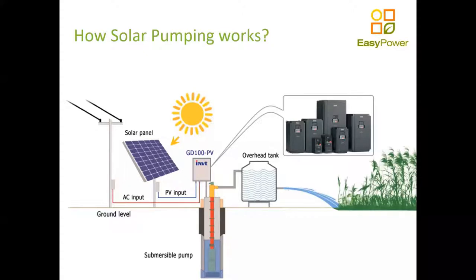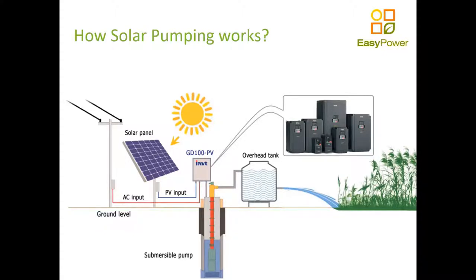The pump inverter drives the pump by changing the frequency, voltage, and output. When utilizing the AC input, it does a double conversion: first rectifying the power into DC at 230 volts, 50 hertz fixed, then feeding that into the DC bus, and then the inverter takes that and supplies a variable output as the pump requires. The third function is being an MPPT — some models have a maximum power point tracking circuit, allowing them to smartly squeeze more power out of the hours of the day.